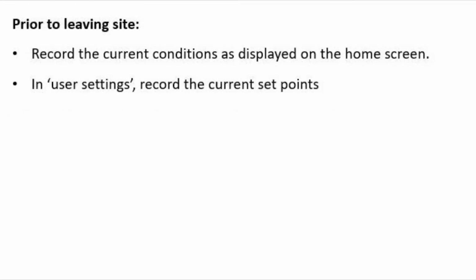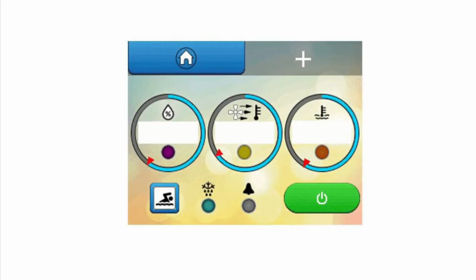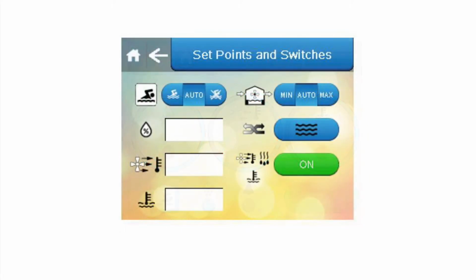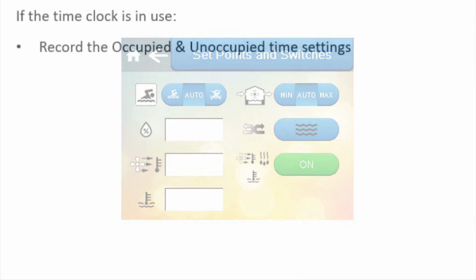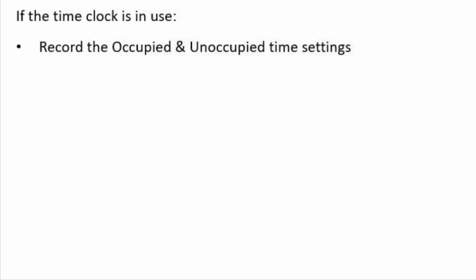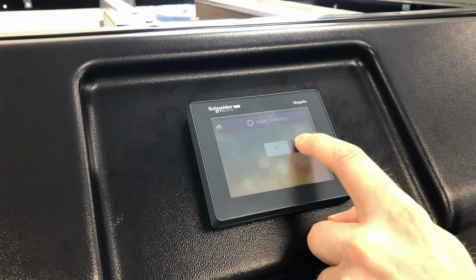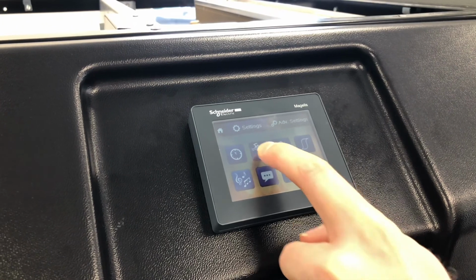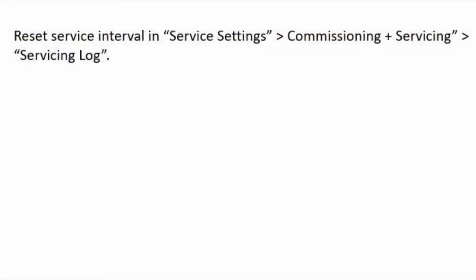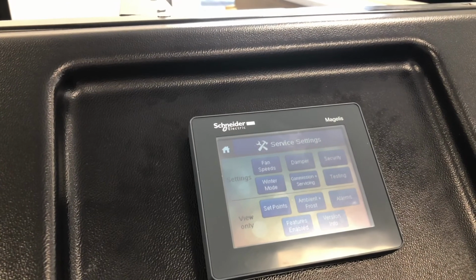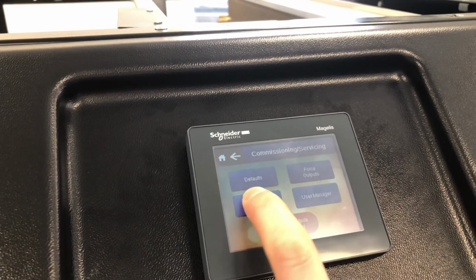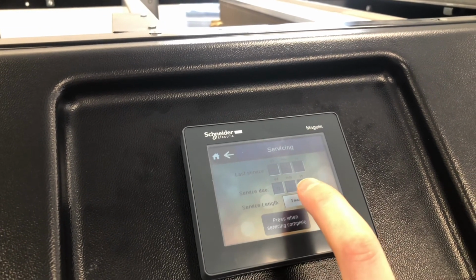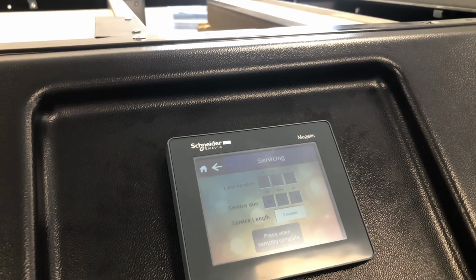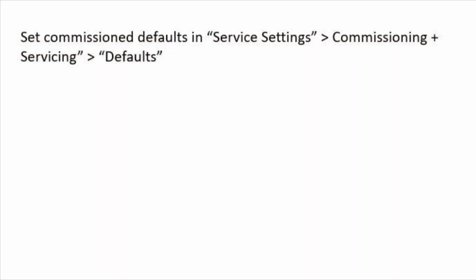Prior to leaving site, it is time to take the final air, water and humidity set points to complete your report. Again, these are located on the home screen and can be recorded in the set point menu in user settings. If the time clock is in use, record the occupied and unoccupied time settings as demonstrated. Reset the service interval in the servicing log. And finally, set the commissioned defaults in the default section in the service settings.